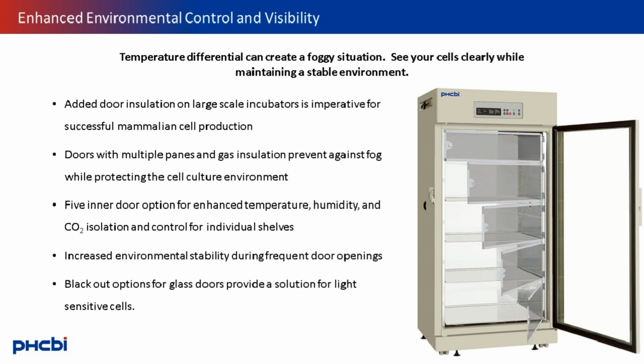It's important that large incubators provide superior insulation while also providing a clear view to minimize door openings. A double-panel gas-insulated door provides the added insulation needed to protect the cell culture environment while also providing a clear view. For added control, a five-inner door option allows for isolation between the solid shelving. It's also great for frequent door openings. When considering the best door options, it's also important to consider a blackout option for large incubator doors if cell lines are light sensitive. Having a well-designed incubator door with the right options in place is a big part of ensuring a stable, uniform environment for your cell cultures.